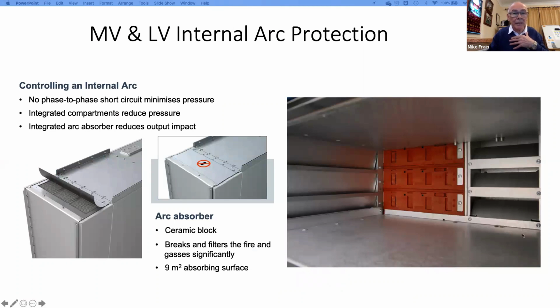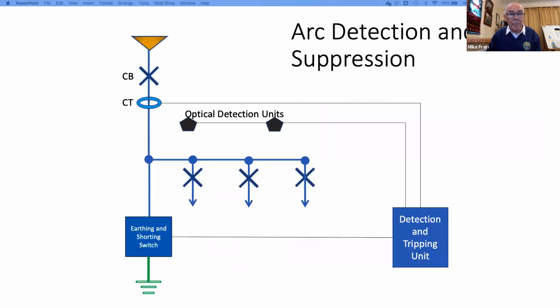Lots to say, but not for today, on MV and LV internal arc protection. Within the IEC standard, it happens to be 62271, for high voltage switchgear, there are standard characteristics to test equipment itself, but as of yet, none of that is mandatory. You have to ask for it, basically.